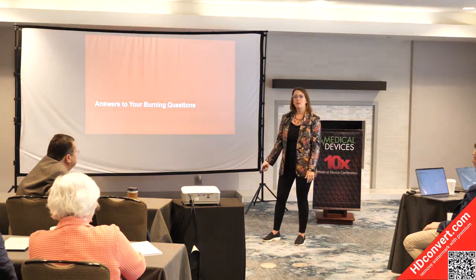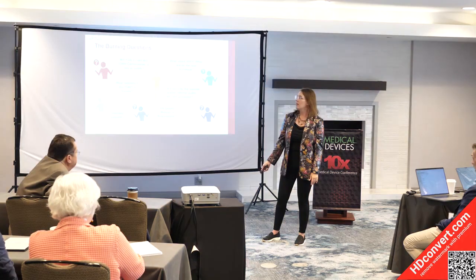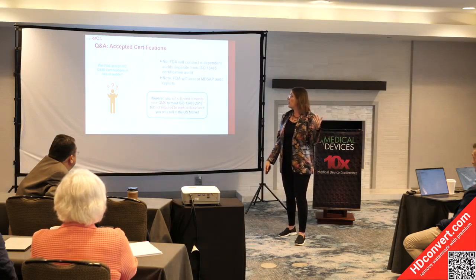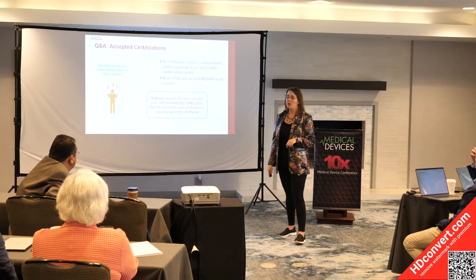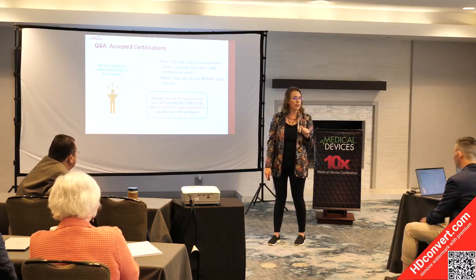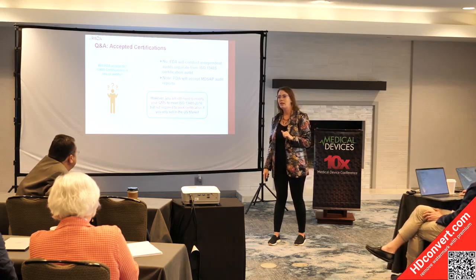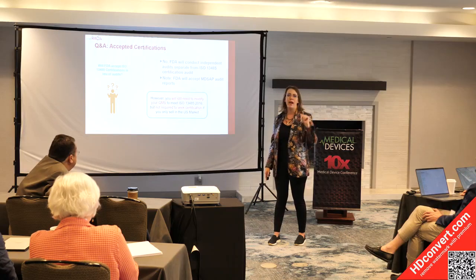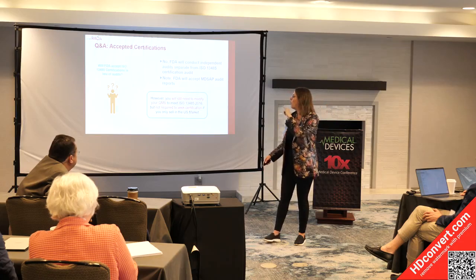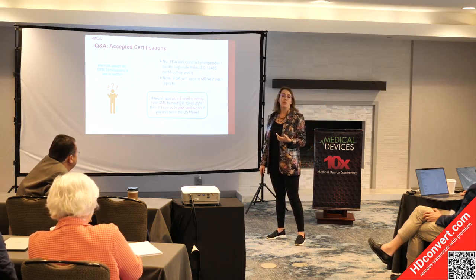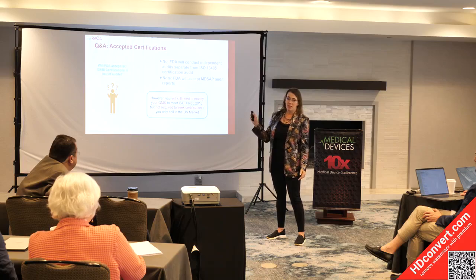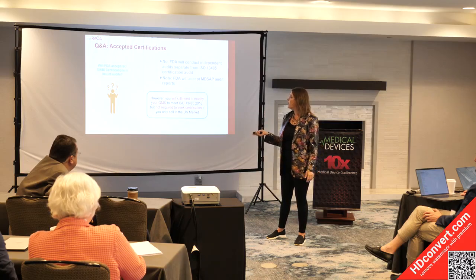Will the FDA accept ISO certifications in lieu of audits? The answer is no. They are still not requiring ISO certifications, they will not recognize ISO certifications as presuming QMSR compliance, and having an ISO certificate does not mean you are compliant with the QMSR. The FDA will still recognize ISO certifications, but separately.